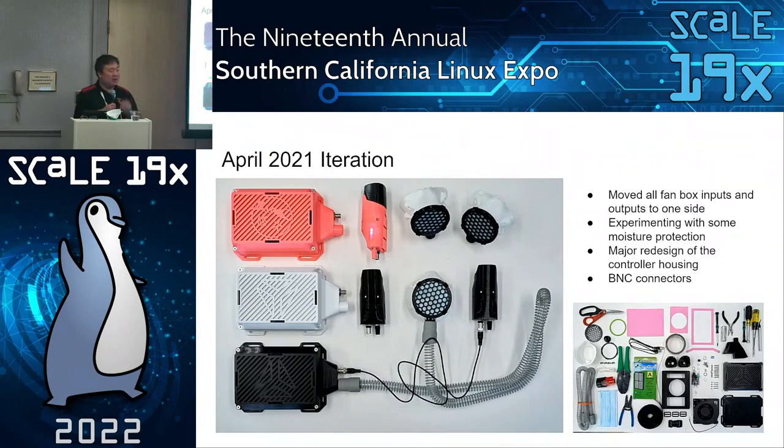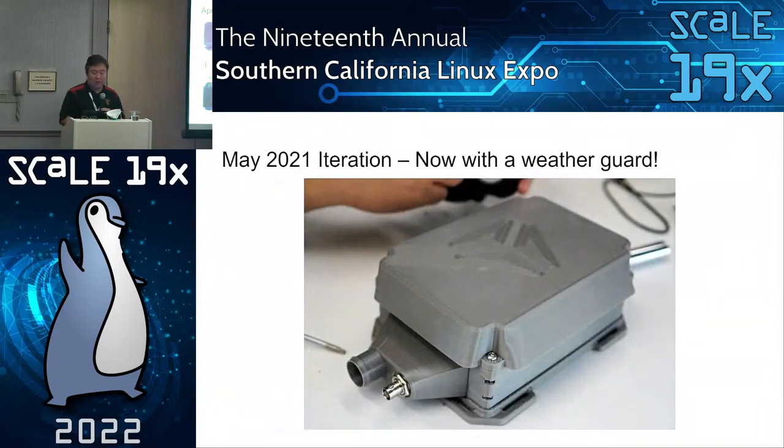We're actually using BNC connectors as our connectors so that they don't disconnect. The important thing here is that we have a power supply that is not firmly attached to our power unit. And what happens when you use just a regular 5.5 millimeter jack? Well, you move a little bit and it pops off, and suddenly you don't have air being pumped to you, which is something that most people don't like, is suddenly having their airflow stopped. So we had to redesign a little bit.